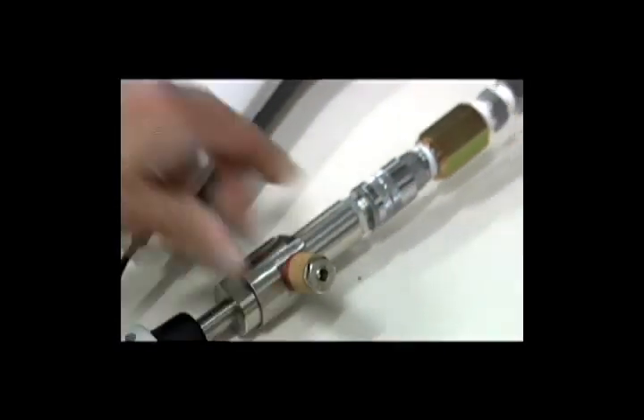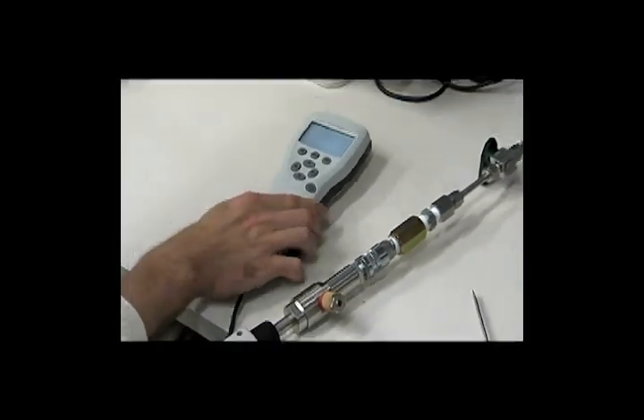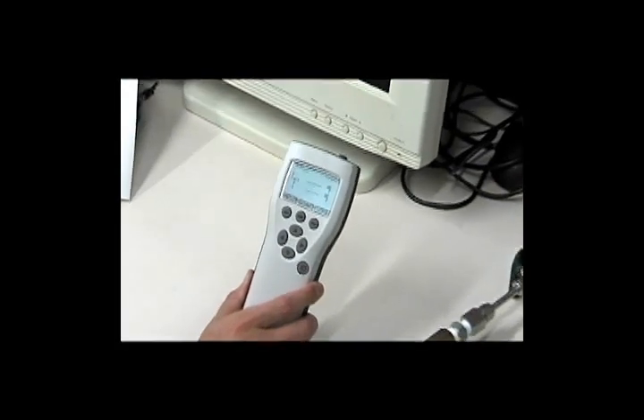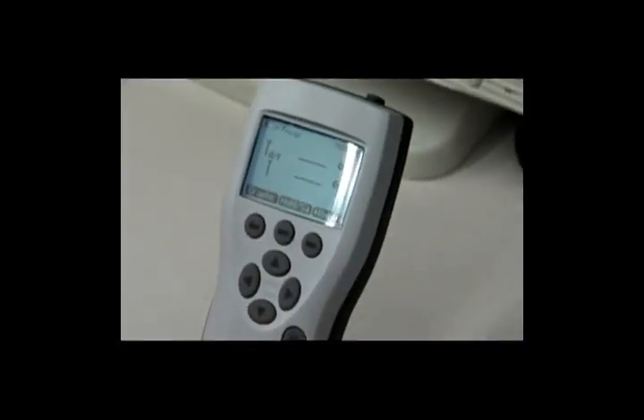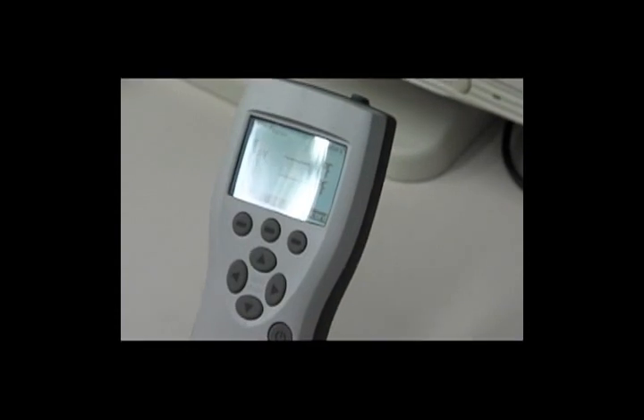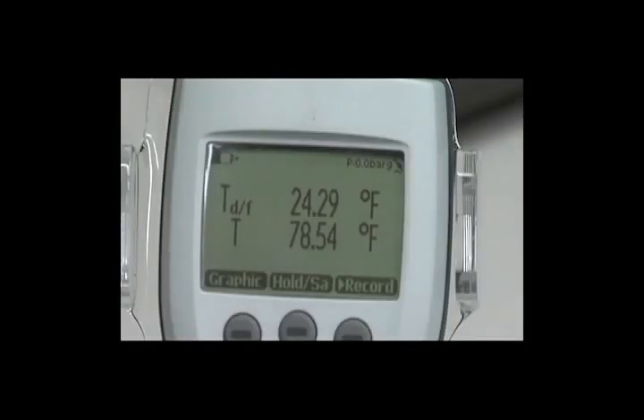This half turn approximates a one liter per minute flow rate, which ensures sufficient air flow to the sensor without creating a significant pressure drop in the sample cell. This is important since dew point is highly pressure dependent. Maintaining consistent pressure between the sample cell and the compressed air line ensures an accurate dew point measurement.